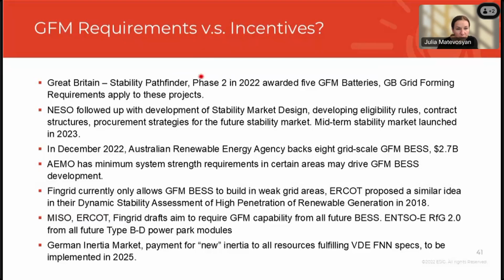Pathfinder already got them. And then in December 2022, the Australian Renewable Energy Agency backed 8 grid-scale grid forming battery energy storage projects. So basically, I believe it's 10% of the capital investment that the Australian Renewable Energy Agency will provide as a subsidy. AEMO also has a minimum system strength requirement in certain areas. And so basically, if you're building a grid following inverter-based resource, it's seen as deteriorating system strength in the area. And that provides extra motivation to maybe bring a grid forming battery next to this resource, or if it's a battery already, maybe build it as grid forming. So it's not a market product, but it's an extra incentive.